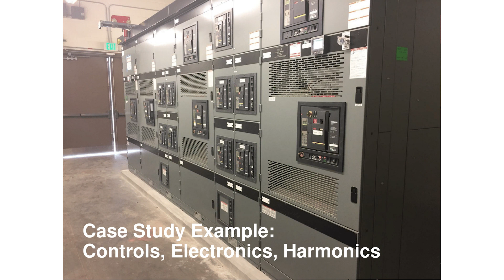My last case study is something we run into a lot - dealing with controls, harmonics, and other electronic equipment. Even though the transfer switches transfer pretty quickly, in the blink of an eye, we still lose power for a second when they switch. That happens when they transfer from normal to emergency, and also when they transfer from emergency back to normal.